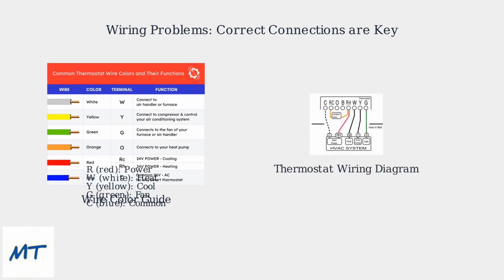This diagram shows how wires connect between the thermostat and HVAC terminals. Each wire must go to its matching terminal to ensure proper operation. Let's highlight the key wires. The red power wire connects to R, white heat to W, yellow cooling to Y, green fan to G, and blue common to C. Incorrect connections can cause serious problems.